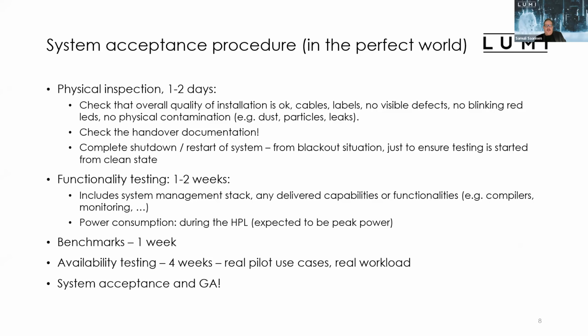A little bit about the system acceptance procedure. This is kind of an ideal, perfect world. When the system is handed over to us, we have a physical inspection, 1 to 2 days. We check the overall quality. We check cabling, labels. We check that there are no visible defects, no blinking red LEDs, no physical contamination like dust or particles, or any leaking pipes. Also, we go through the handover documentation, and then we have a complete shutdown of the system, and we restart the system, and then it's basically a clean start, and we can start our functionality testing.